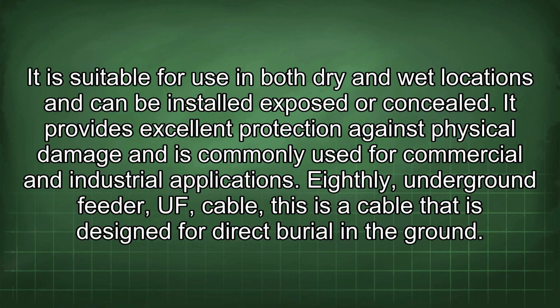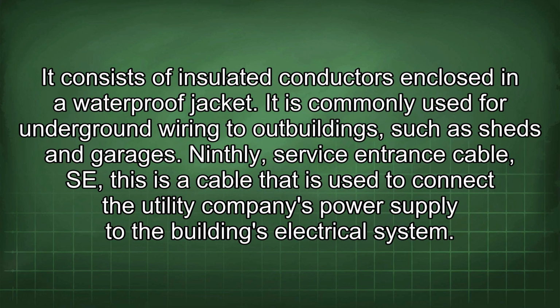Eighthly, underground feeder cable, type UF. This is a cable that is designed for direct burial in the ground. It consists of insulated conductors enclosed in a waterproof jacket. It is commonly used for underground wiring to outbuildings, such as sheds and garages.